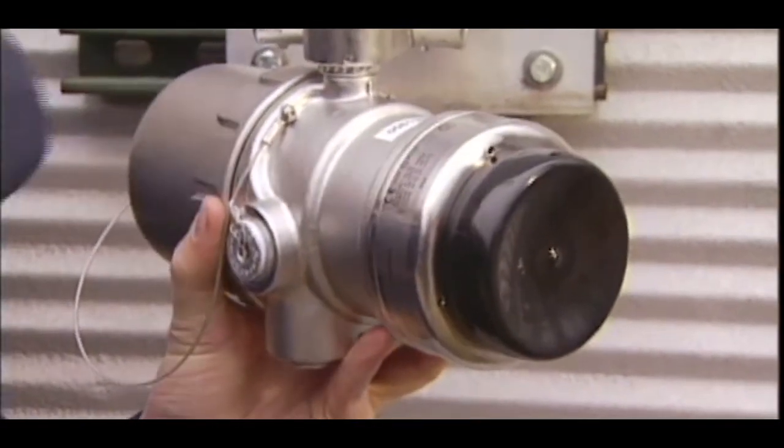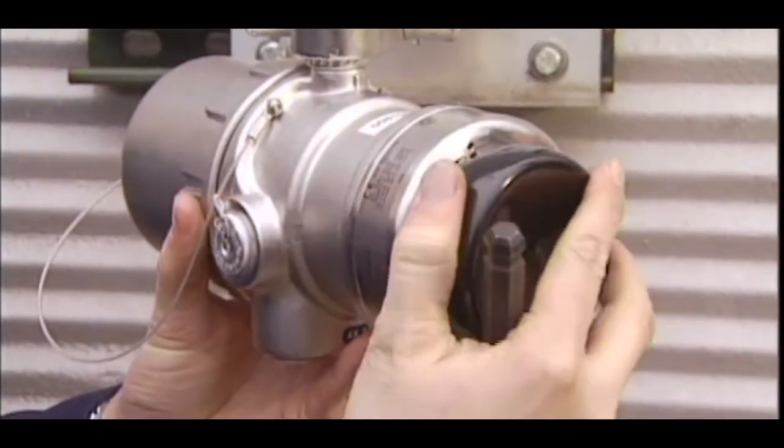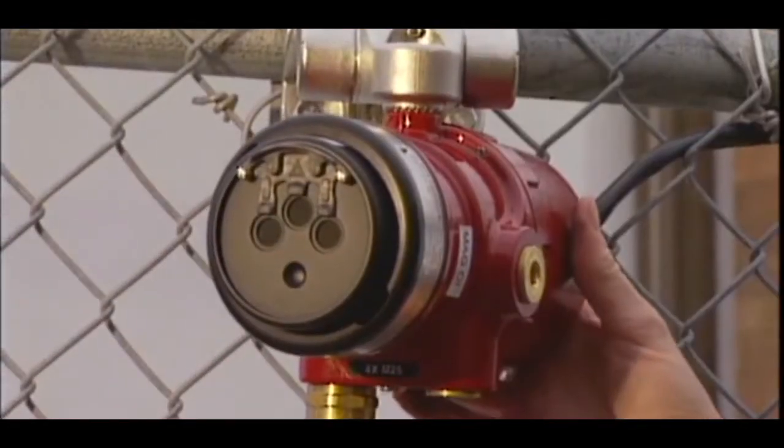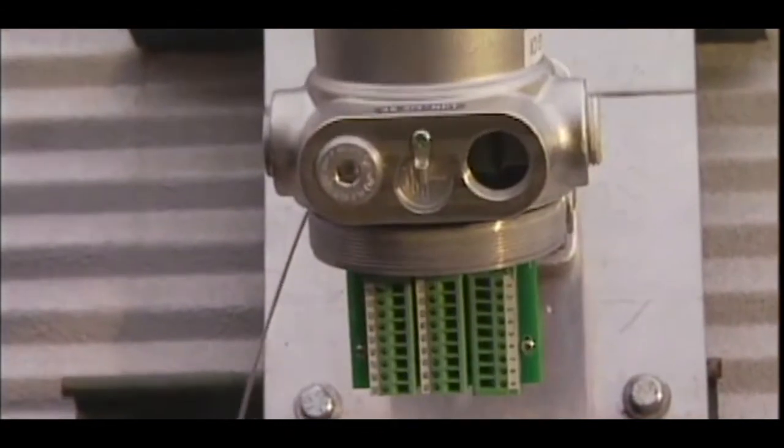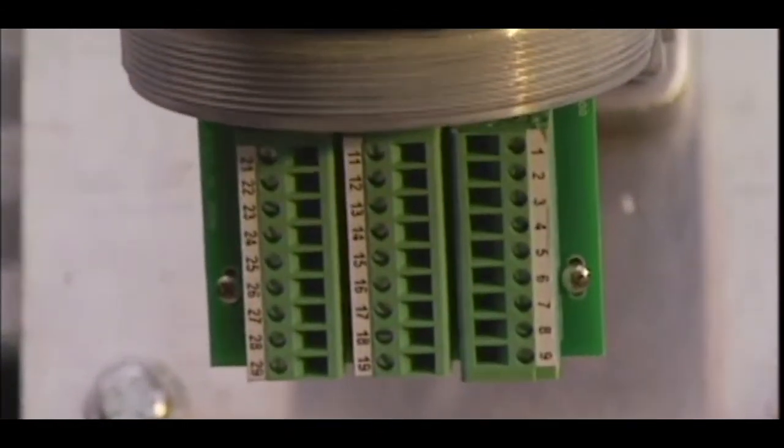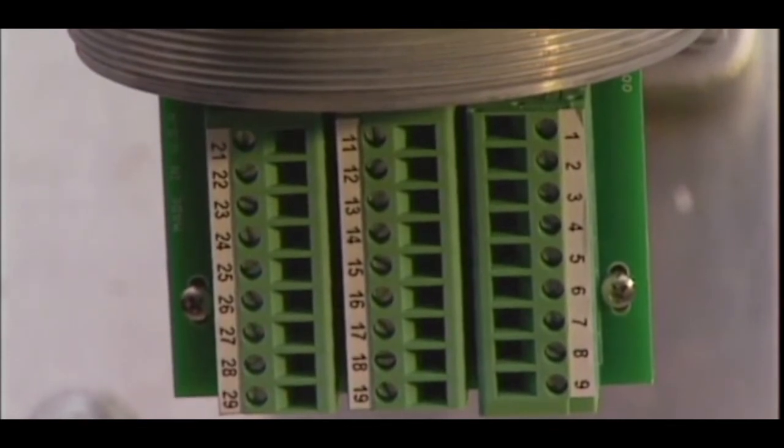The physical design of the X-3301 has been optimized for high performance and ease of installation and is available in either 316 stainless steel or low magnesium, copper-free aluminum. A dedicated wiring compartment is rated both EXD and EXE to allow for the lowest cost installation that meets individual customer requirements.